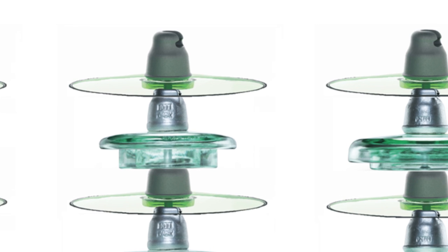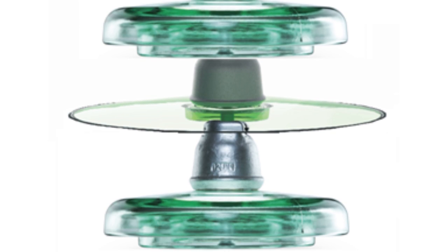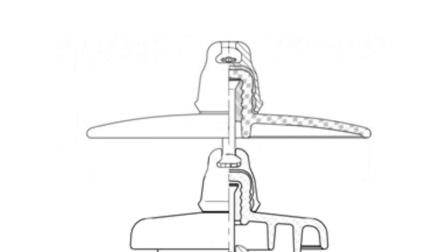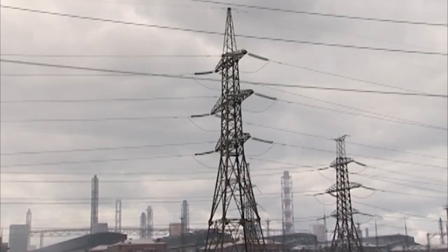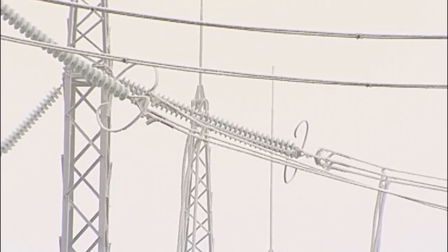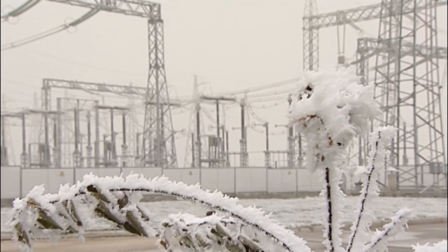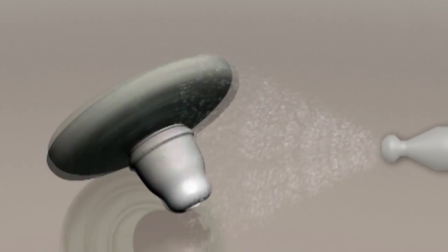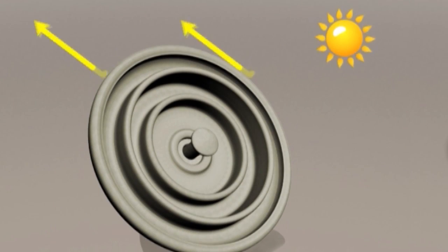For variation of aerodynamic and fog characteristics, interchange of aerodynamic profile insulators with extreme-rib and extended-rib fog-type insulators is used. In cases of salt spray, fat deposits, emissions from industrial enterprises with acid reaction, white frost, and icing, the presence of ribs alone is not sufficient. In such cases, it is better to use a waterproof mixed string.